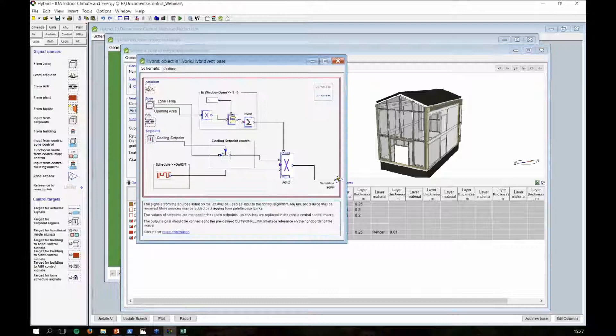The second one, I want to test if my window is open. And the way to do this is to take a signal from this zone module that says opening. And this basically tells me how many square meters of large vertical openings I have. So when my window opens, this number will spike. So I want to take this and test it. Is it open? And then convert it to a signal between 1 and 0. If it is open, then it's a 1. If it's not, then it's a 0. Or sorry, if it is open, it's a 0. I don't want mechanical ventilation. If it's not open, then it's 1.